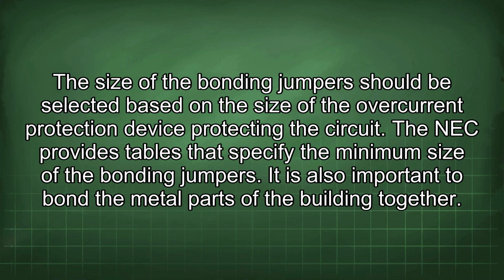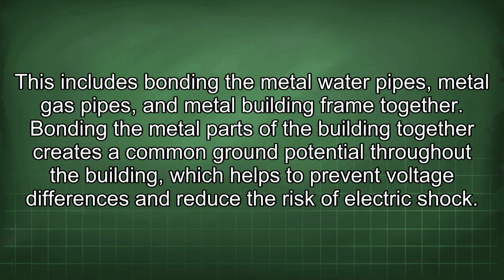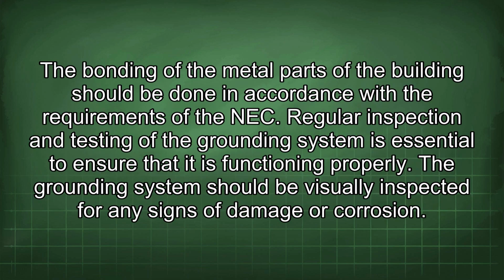It is also important to bond the metal parts of the building together. This includes bonding the metal water pipes, metal gas pipes, and metal building frame together. Bonding the metal parts of the building together creates a common ground potential throughout the building, which helps to prevent voltage differences and reduce the risk of electric shock. The bonding of the metal parts of the building should be done in accordance with the requirements of the NEC.